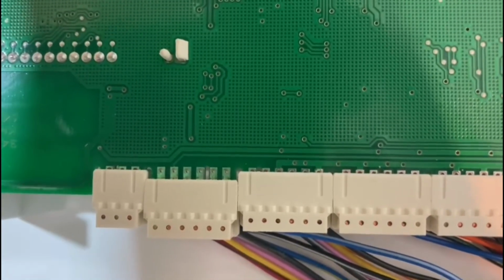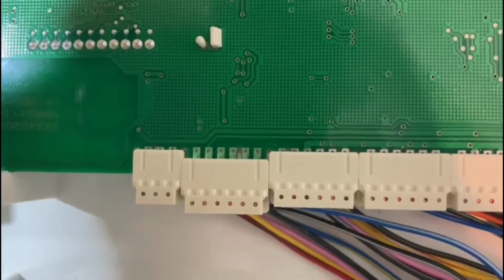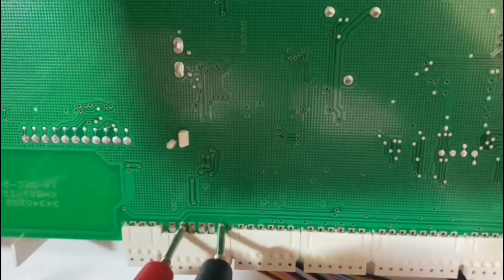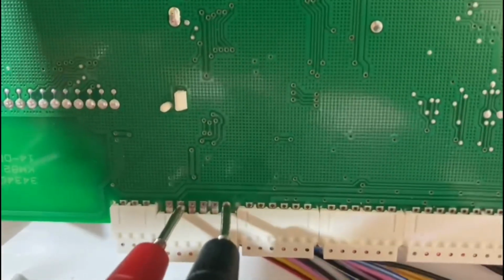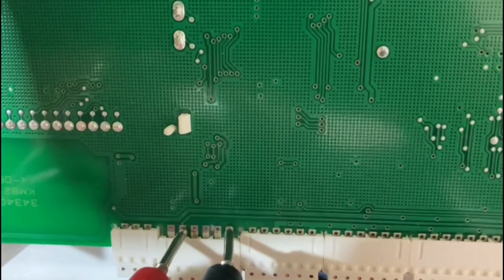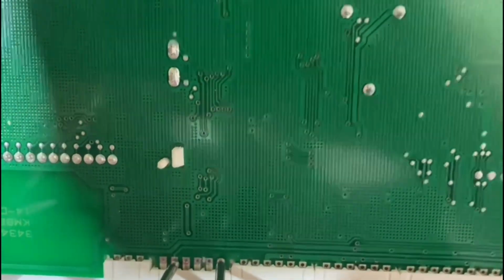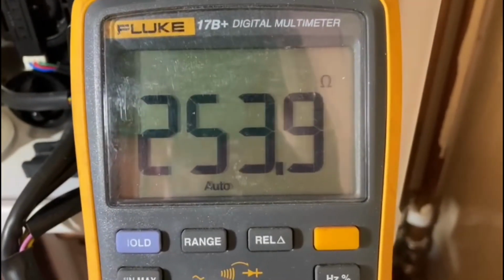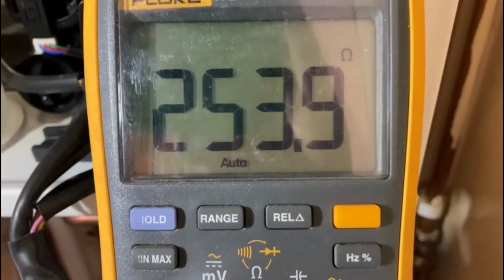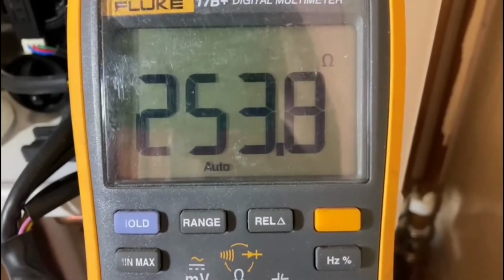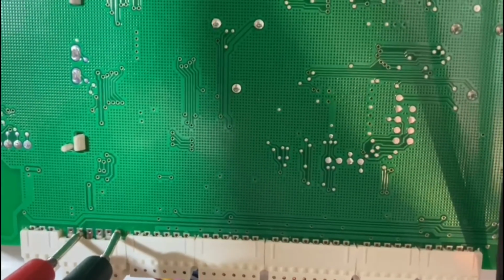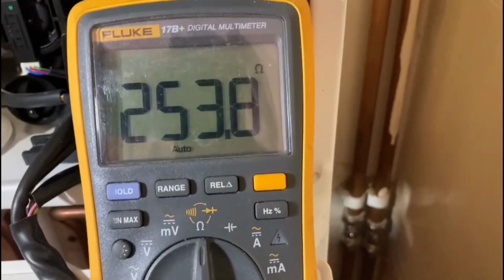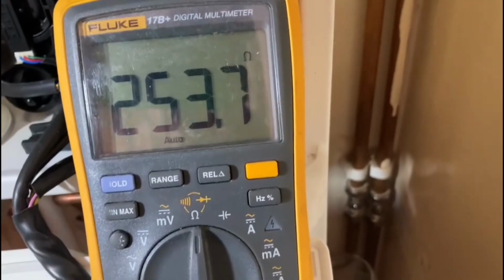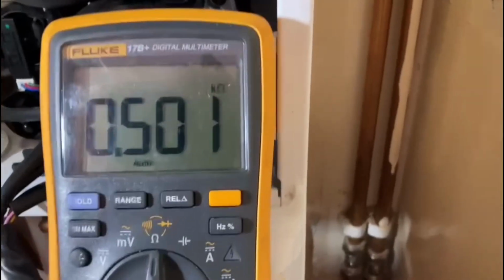I'll set it up now and show you a single test, then testing them together. I've got it on the right connector on the 24-volt supply, testing the single black power to the coil, and we're getting 253 ohms. You'll get roughly the same across the blue one next to it. Then I'll test them together, and you should get double that - around 500. Let me set that up. There you go, 500.